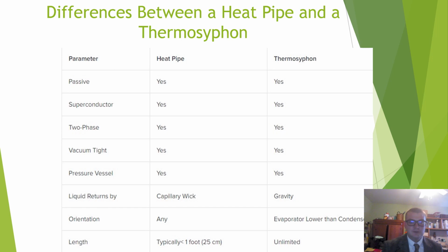However, this is where the differences begin. The liquid in a heat pipe is returned by a capillary wick, as opposed to the thermosyphon, which is returned by gravity. Because of that, a large amount of thermosyphon design hinges on the fact that the evaporator must be lower than the condenser.